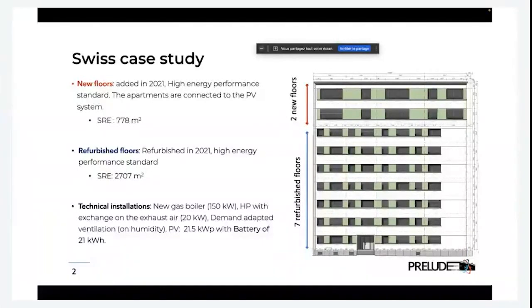All the technical installations were also refurbished: a new gas boiler, quite powerful for a building so well insulated, but that's because it was also meant to operate during the work performed on the building, so it had to produce enough heat for a non-insulated building. There's also a heat pump with heat exchange on the exhaust air of the ventilation, and that ventilation is demand-controlled, depending on the humidity of the rooms it ventilates.